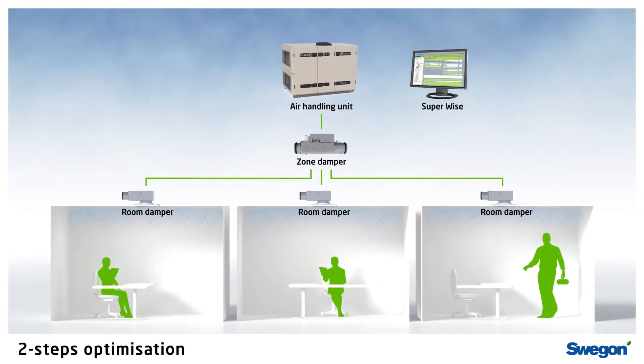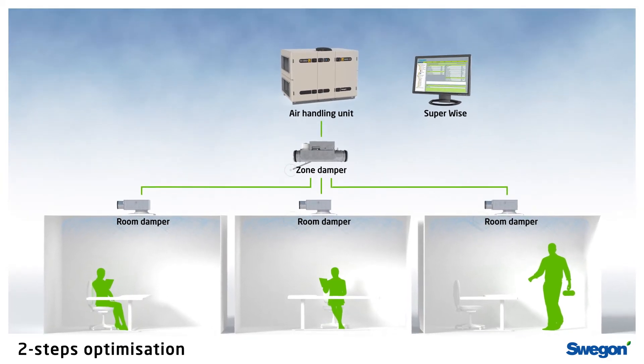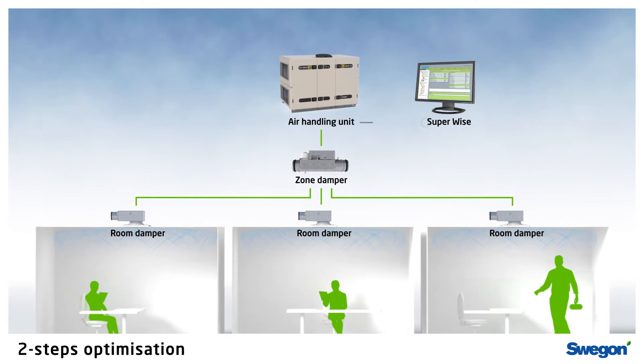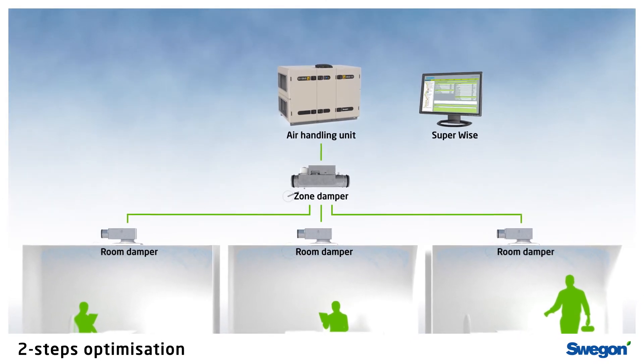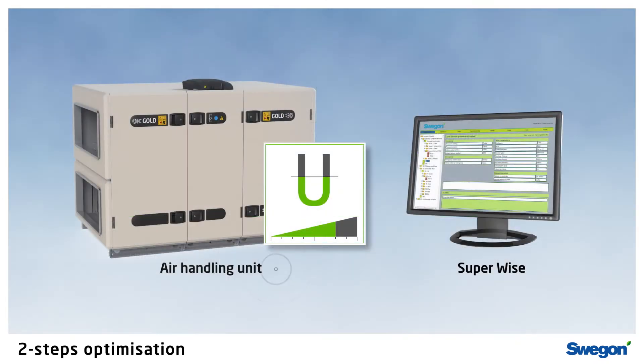Two-step optimization is used to minimize pressure drop throughout the ventilation system, which means that Superwise adjusts the air handling unit's pressure set point based on the dampers in the rooms and in the zones.